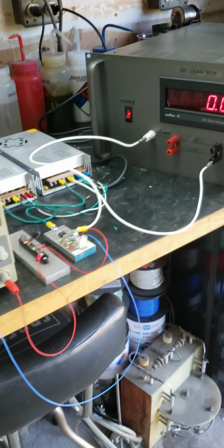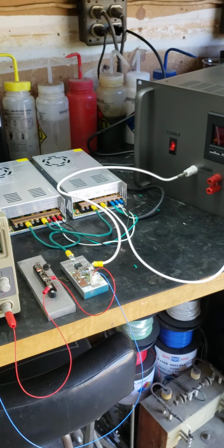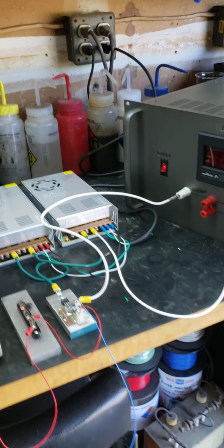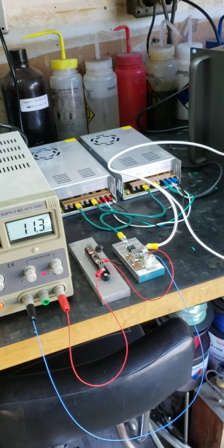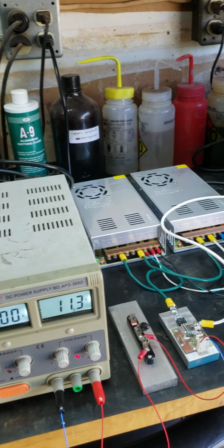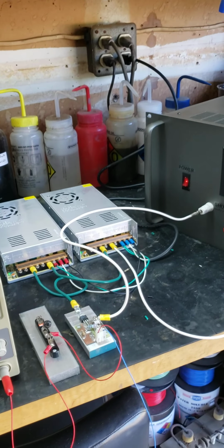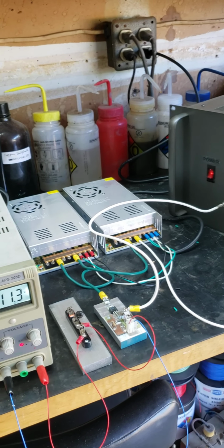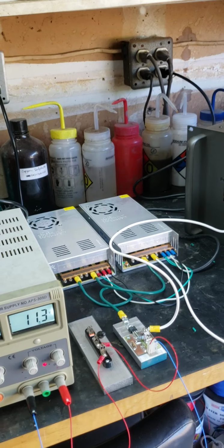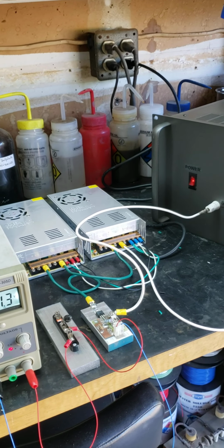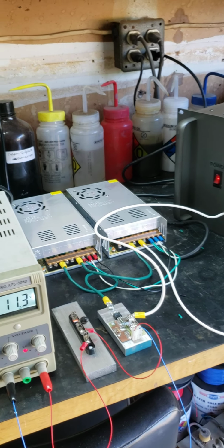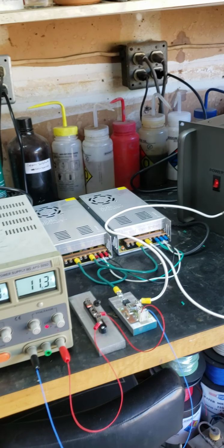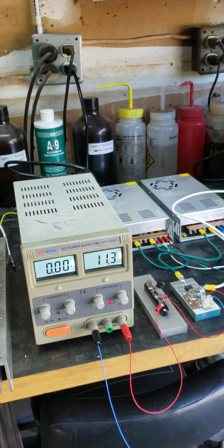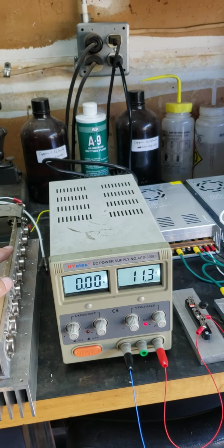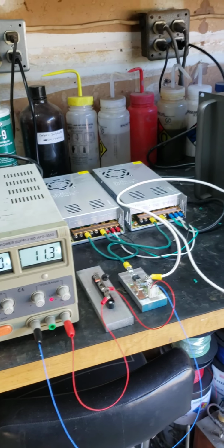Anyway, so I got the 1500 VA transformer, which is what this is going to require. Maybe closer to 1700 VA, but it's not going to put out 1700 VA. It'll probably put out 1450 and be real close to the spec, and buzz like a son of a bitch at 1500 VA, because they get really buzzy when you start saturating the core.